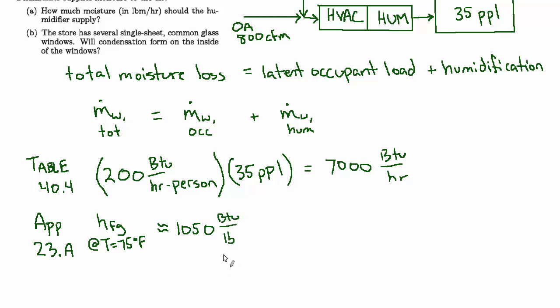So let's just say this is approximately 1050 BTU per pound, and that's BTU per pound of water, of course, because we're talking about water vapor. And now we can use the fact that the latent heat, which has energy units—that's the 7,000 BTU per hour—is equal to the mass flow rate of water times the latent heat of vaporization. So now we know this and we know this, we can solve for ṁ.